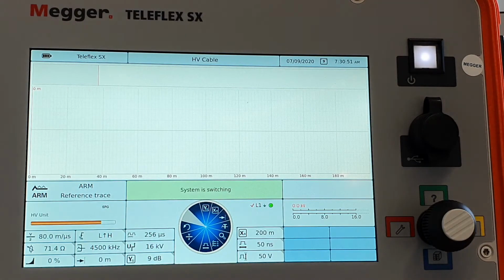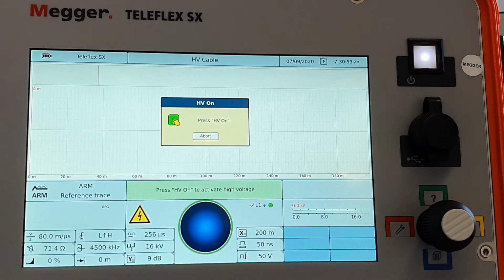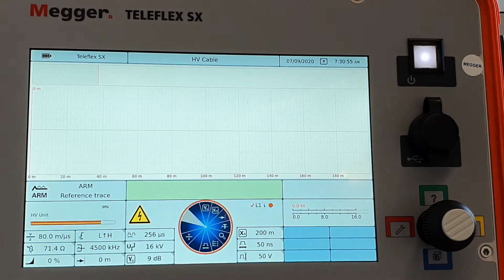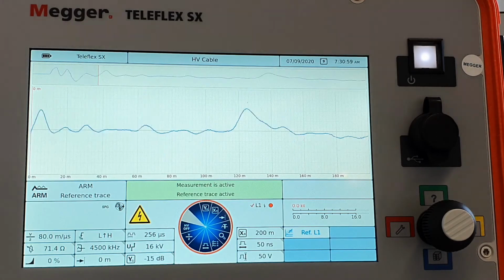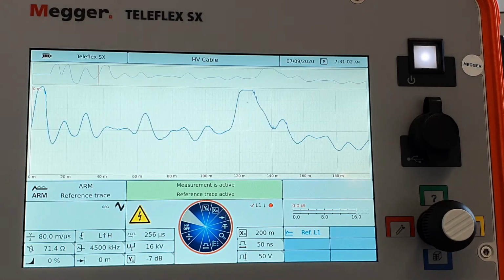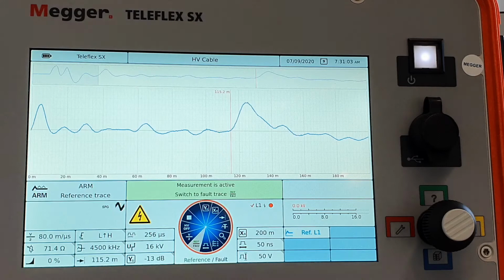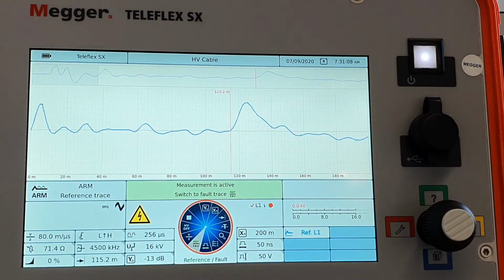You hear the switching of the instrument again. Press the high voltage. That's always the same procedure in any mode. Automatically it is finding the cable end here as an upward reflection and setting the range and the gain. I switch over to fault trace.